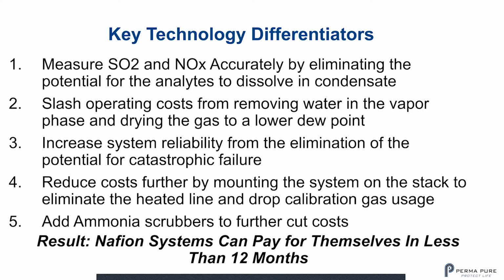We reduce costs further by mounting the system on the stack to eliminate the heated line and drop calibration gas usage. And we can add ammonia scrubbers to further cut costs if you're working with any systems that have ammonia in the gas. The result is that Nafion systems can pay for themselves in as little or less than 12 months.